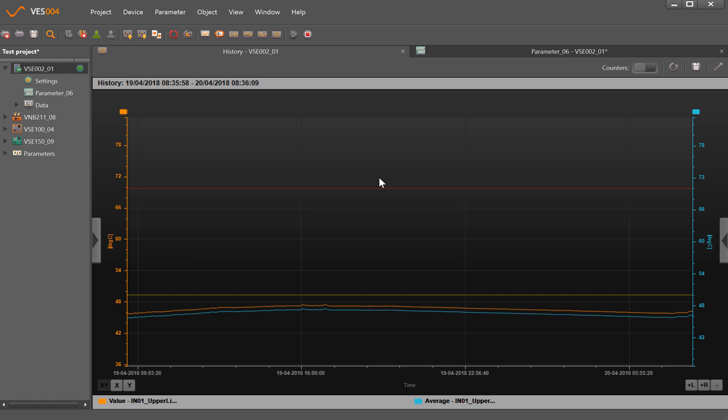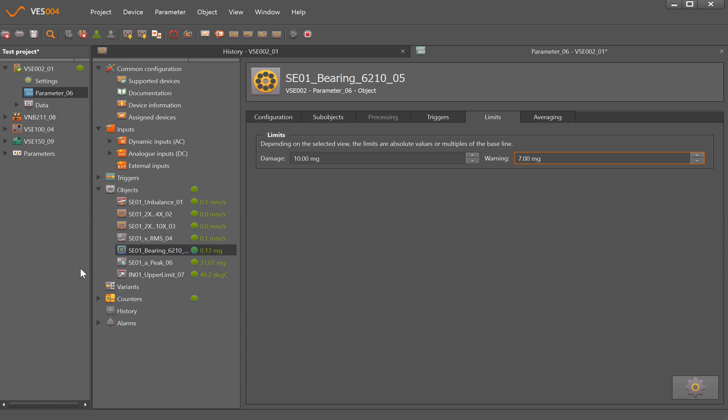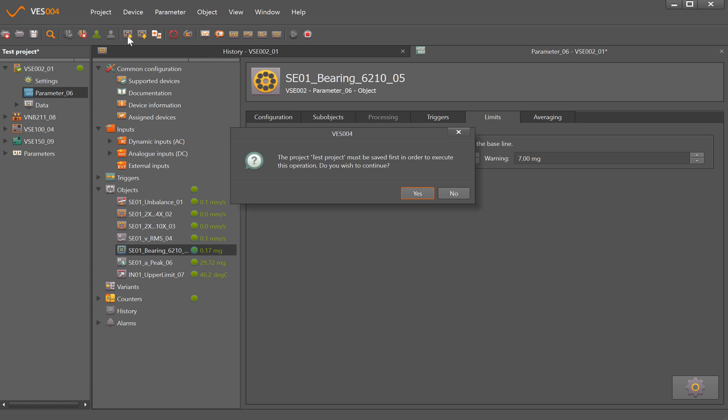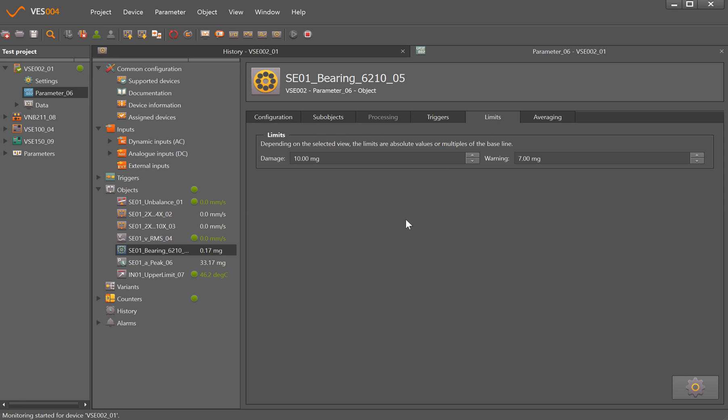So the only what I'm looking to change here will be the bearing levels. So we've gone into the parameter set and we've changed those, but the thing you need to remember whenever you make any changes is to come up to the top here and write parameters to device. So as soon as we click on that, yes we do want to continue. What that's now done is change the alarm levels for the bearing to something that's much more suited to the application.